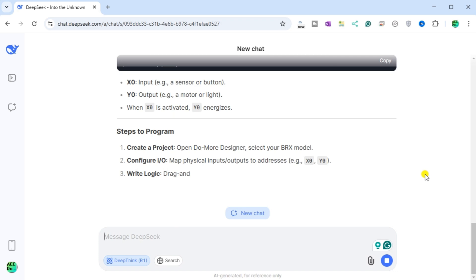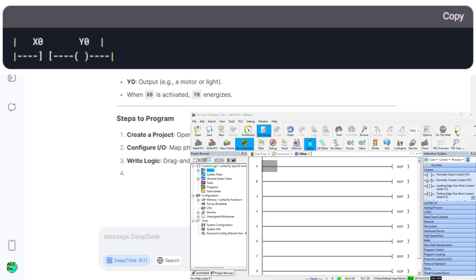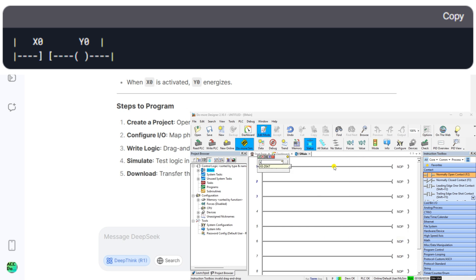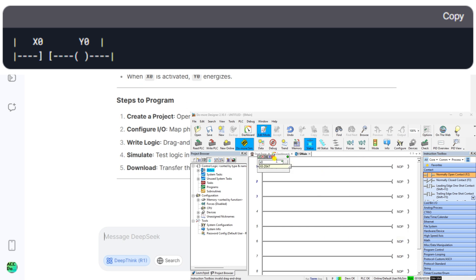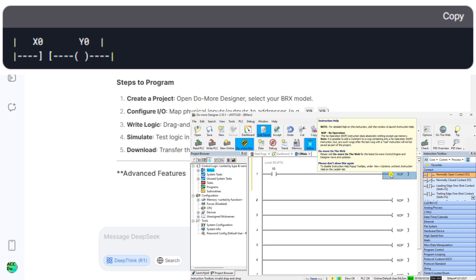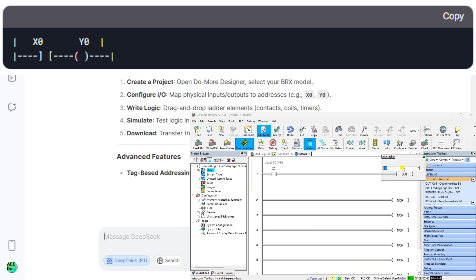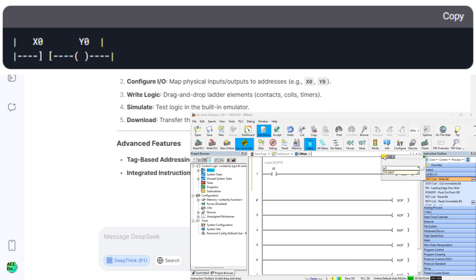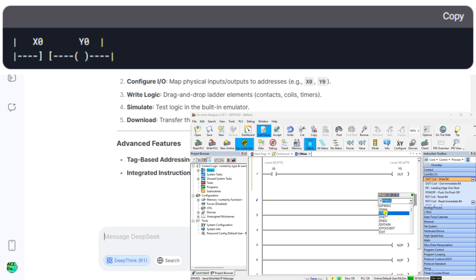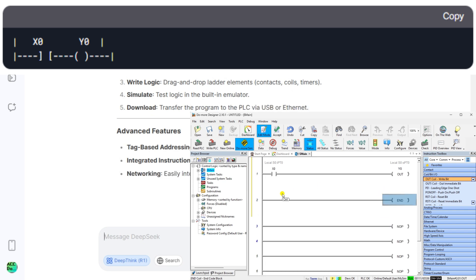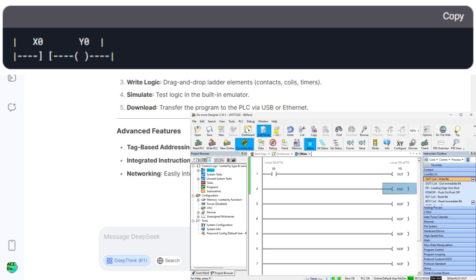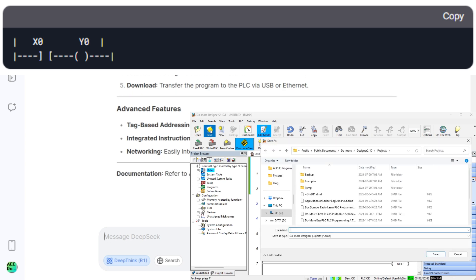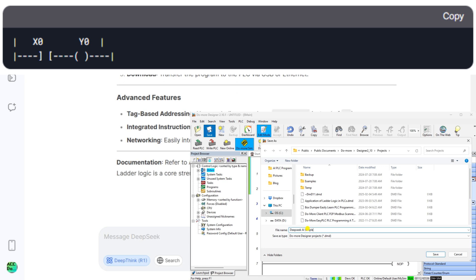Simple example — turn on an output with an input. Ladder rung: X0 (input, e.g. a sensor or button) drives Y0 (output, e.g. a motor or light). When X0 is activated, Y0 energizes. Steps to program: Create a project, open DoMore Designer, select your BRX model, configure I/O by mapping physical inputs/outputs to addresses like X0 and Y0, write logic by dragging and dropping ladder elements — contacts, coils, timers — then simulate using the built-in emulator, and download to the PLC via USB or Ethernet.